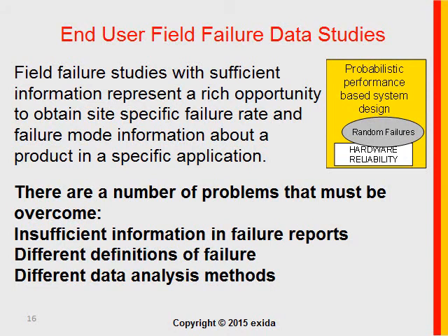End-user field failure data studies, on the other hand, I've said represent the highest potential for good field failure rate data, but we must overcome a number of problems that we have found to be quite chronic, including insufficient information in the failure reports, different definitions of what is a failure, and different data analysis methods. But these problems can be solved, as I will talk about some more.